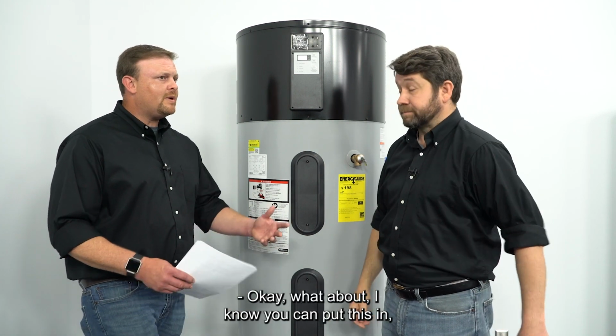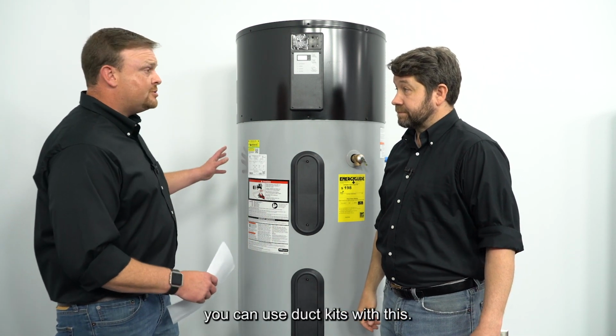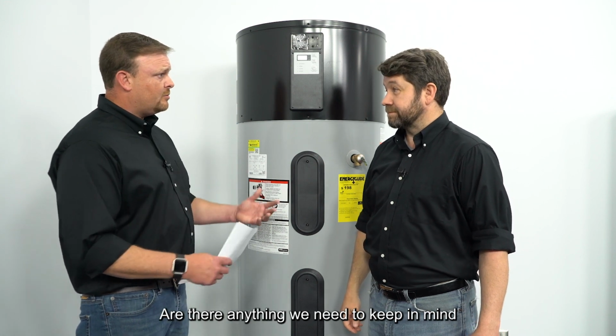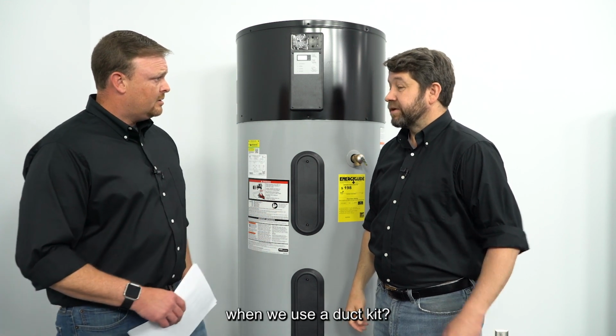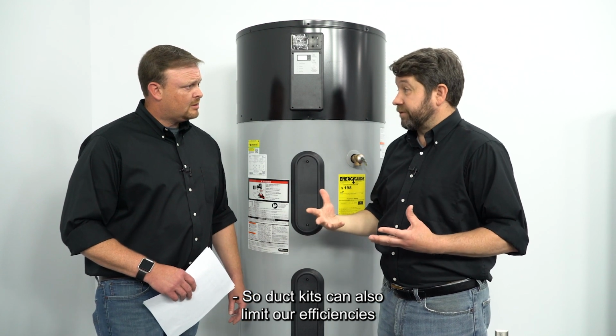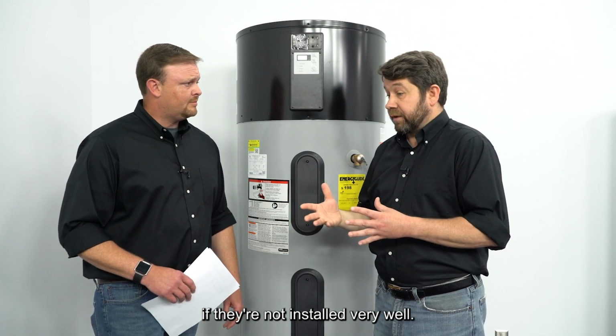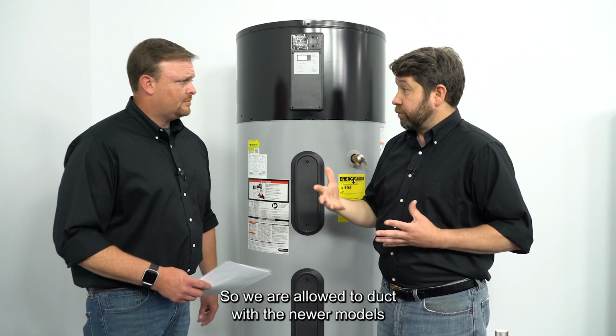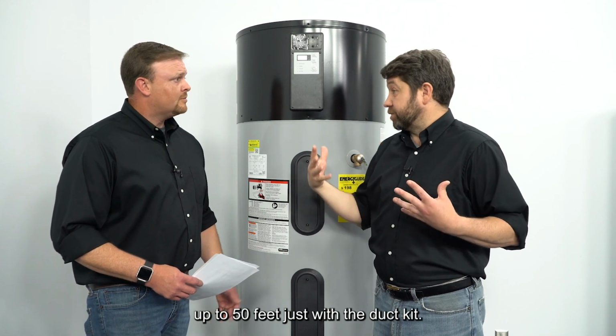Okay, what about, I know you can put this in, you can use duct kits with this. Is there anything we need to keep in mind when we use a duct kit? So duct kits can also limit our efficiency if they're not installed very well. So we are allowed to duct with our newer models up to 50 feet just with the duct kit.